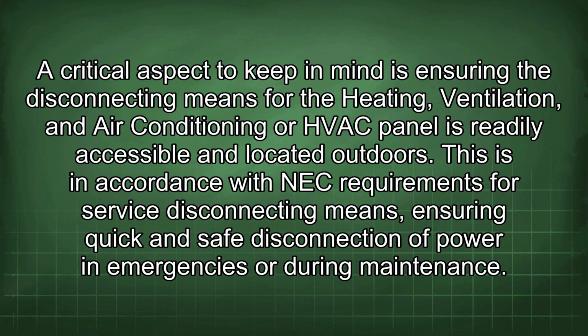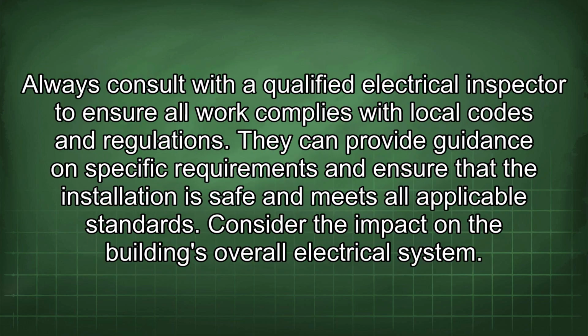A critical aspect to keep in mind is ensuring the disconnecting means for the heating, ventilation, and air conditioning or HVAC panel is readily accessible and located outdoors. This is in accordance with NEC requirements for service disconnecting means, ensuring quick and safe disconnection of power in emergencies or during maintenance. Always consult with a qualified electrical inspector to ensure all work complies with local codes and regulations. They can provide guidance on specific requirements and ensure that the installation is safe and meets all applicable standards.